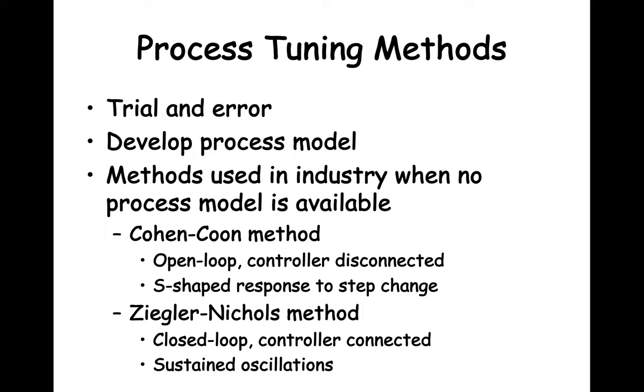The method to use will depend on whether the controller is disconnected during tests run to collect data needed, or whether the controller is connected. If you use the open loop method, the controller is disconnected and the response will be S-shaped — you will be using the Cohen-Coon method. If you use the closed loop method, the controller is kept in the process control system, the response wanted is sustained oscillations, and you will be using the Ziegler-Nichols method.